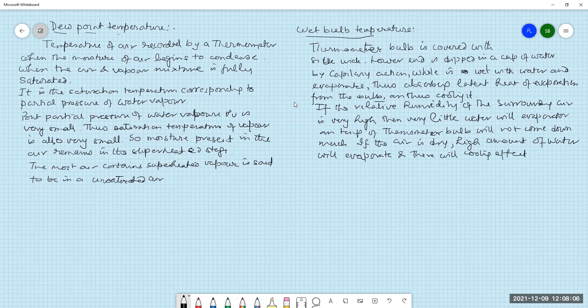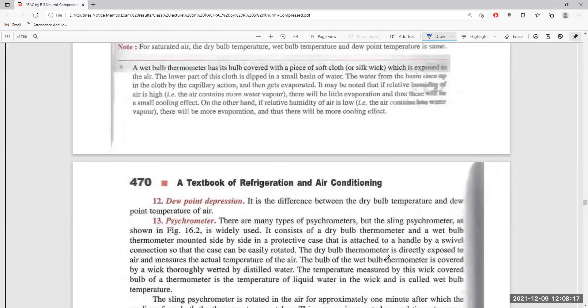Next comes dew point depression. It is the difference between the dry bulb temperature and the dew point temperature of air. There is also wet bulb depression, which is the difference between dry bulb and wet bulb temperature. Dew point depression is the difference between dry bulb temperature and dew point temperature.